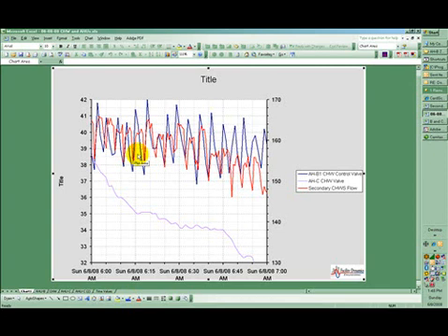The other issue here, aside from the fact that we're setting up a pattern that is setting us up to trip the chiller, four cycles an hour, over 150,000 cycles a year. Well, the design life on the Belimo actuator that I believe is on that valve is about 60,000 cycles. And so we're setting ourselves up to wear the actuator out, wear the packing glands out, basically for a long-term O&M issue that'll probably come up in the warranty period.